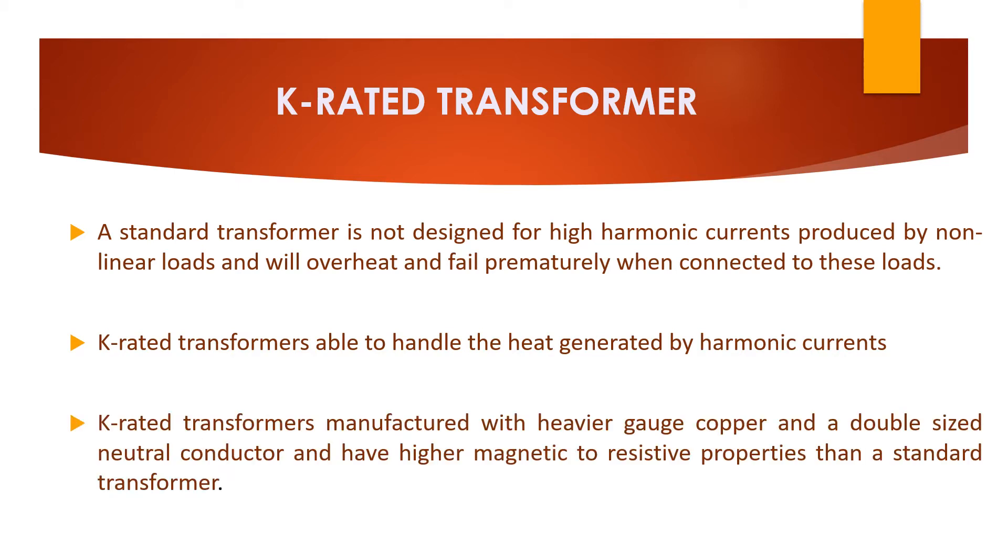So how it is manufactured? K-rated transformer manufactured with a heavier gauge of copper and a double-sized neutral conductor and also higher magnetic to resistive properties than a standard transformer. So that this can withstand harmonic currents which are produced by non-linear loads.